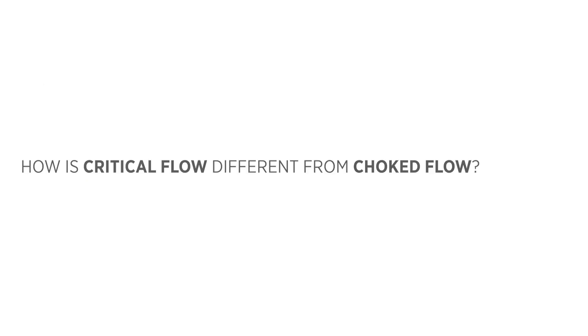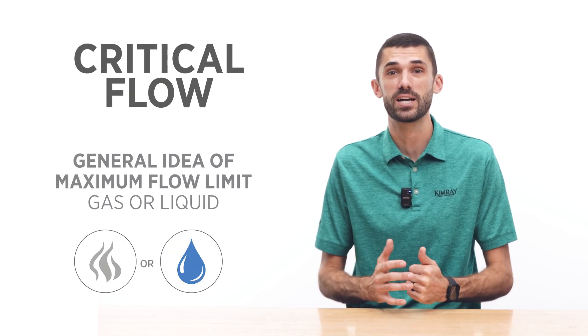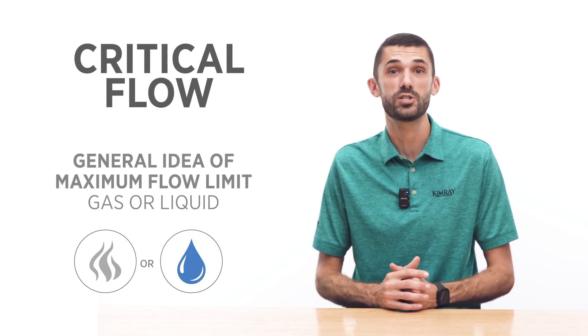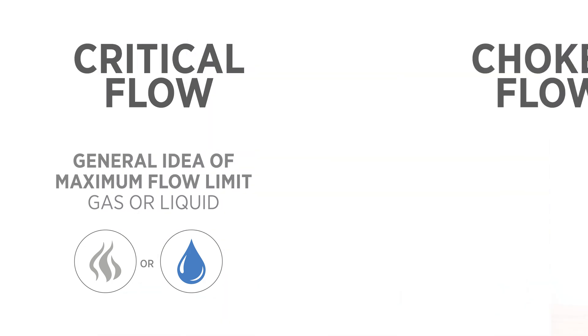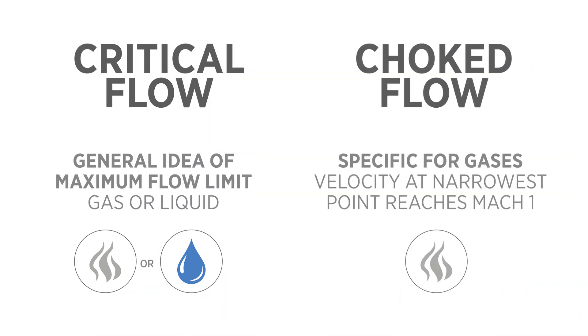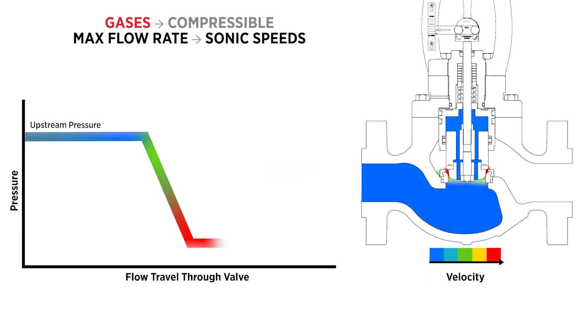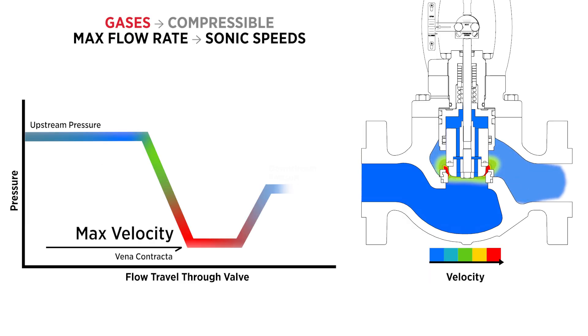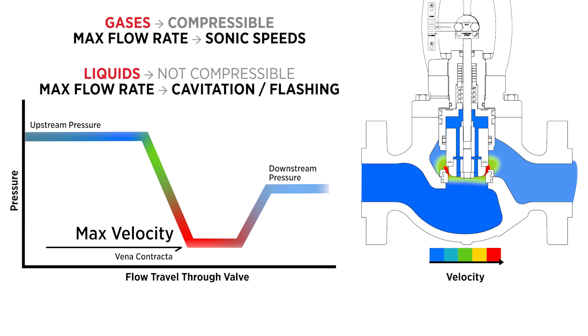The terms are often used interchangeably, but here's the distinction. Critical flow is the general idea of a maximum flow limit, and it applies to both gases and liquids. Choked flow is the specific case for gases, where velocity at the narrowest point reaches Mach 1, or the speed of sound. Since gases are compressible, they reach sonic speeds at a restriction. Liquids don't normally do this, so true choked flow doesn't occur. Instead, liquids reach maximum flow rate due to cavitation or flashing, not Mach 1 speeds.